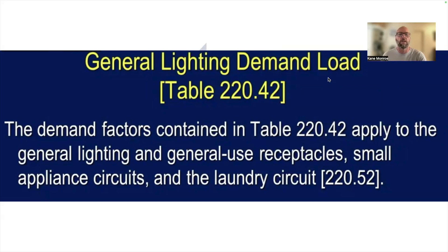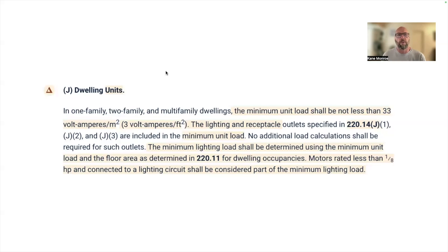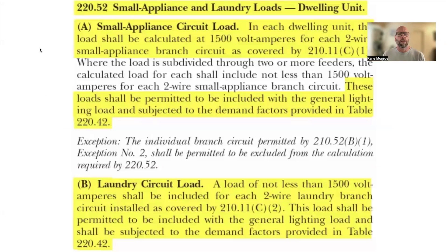For one-family, two-family, or multi-family dwellings, the minimum unit load shall not be less than 33 volt-amperes per square meter or 3 volt-amperes per square foot. That's standard and does not change throughout the 2017 through 2023 NEC. In Section 220.52, this is where we find our small appliance and laundry circuit loads.